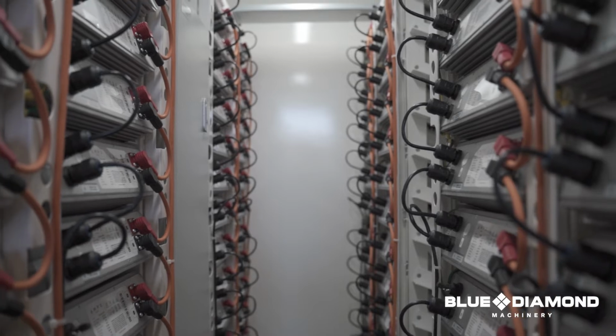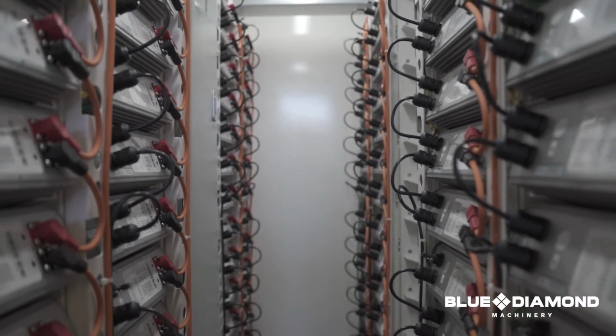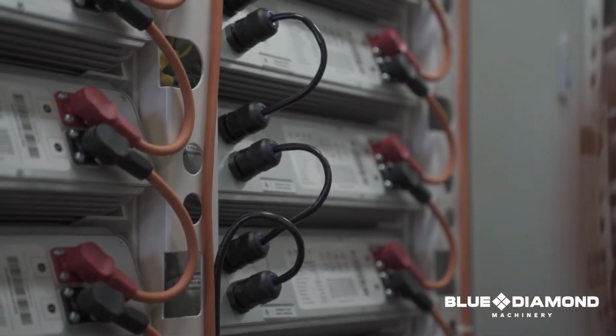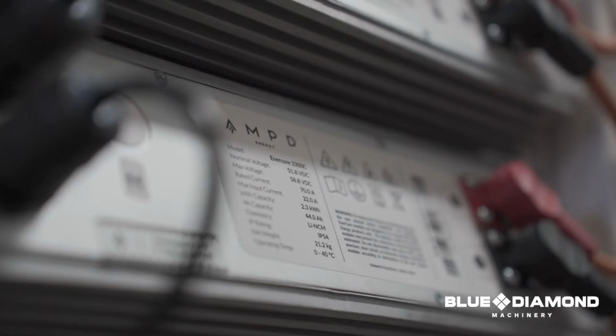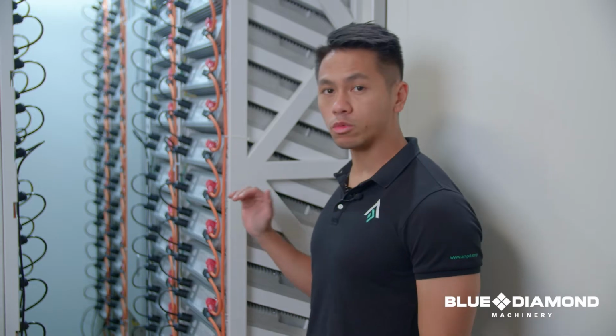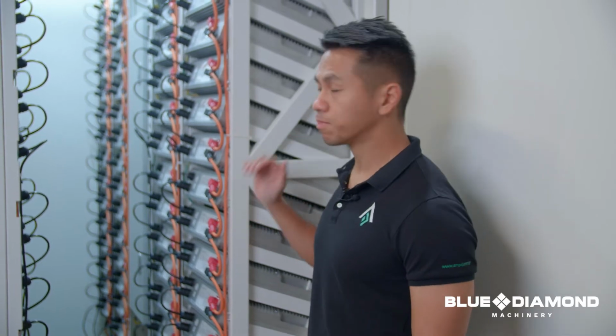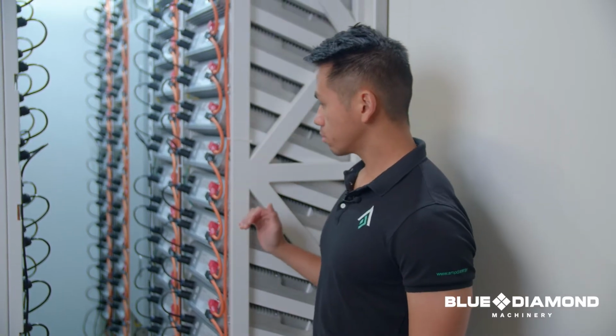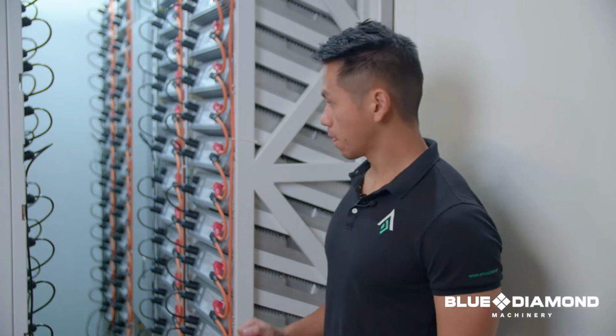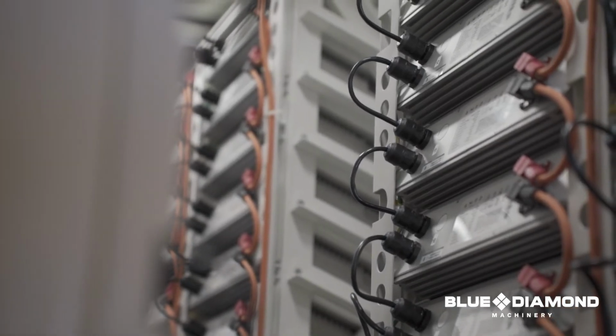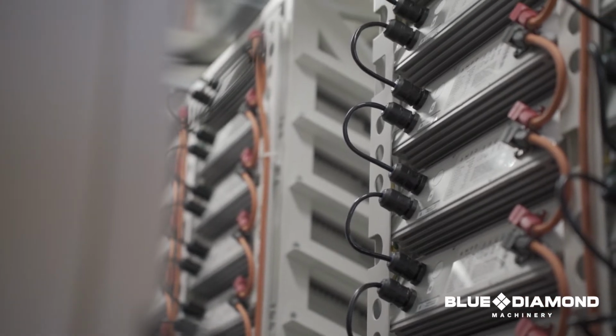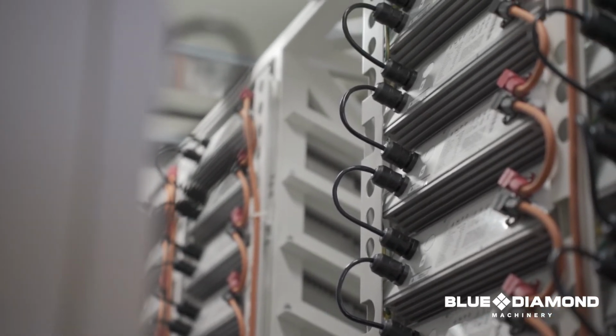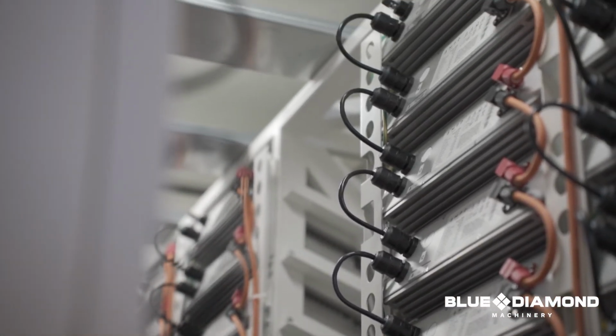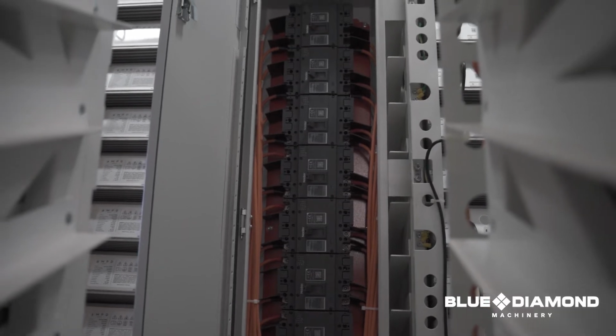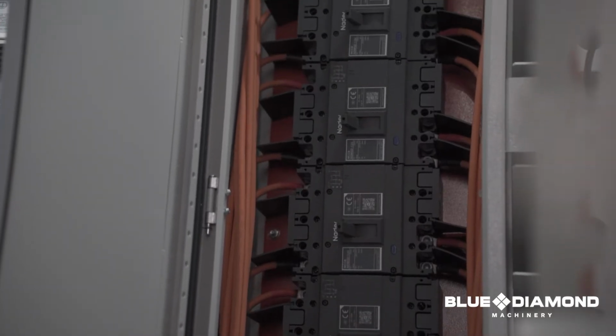Our battery modules, 15 of them, are fitted into one column, which we define as one string. Every string will be connected in series. There are a total of 8 strings inside this room, which are in parallel with each other. The concept of that is if one string drops off for any reason whatsoever, the other strings will continue to run with no disruption.